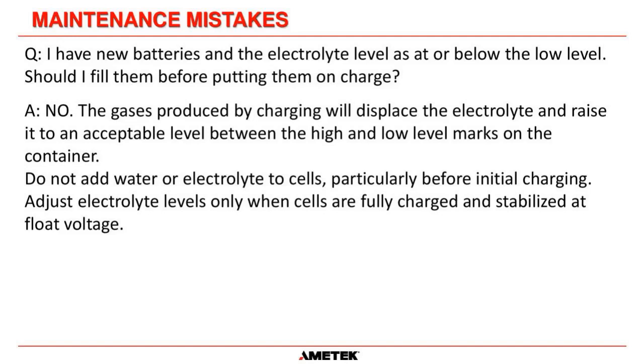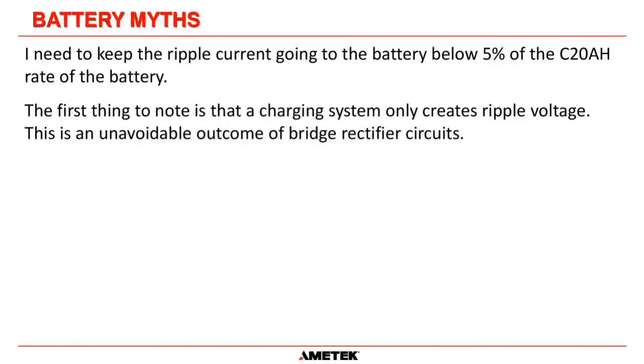So when you charge the plates, that sulfuric acid gets dispelled from the plate itself and increases the level of the electrolyte also. So do not add water or electrolyte to cells, particularly before your initial charge. Only adjust electrolyte levels when the cells are fully charged and stabilized at float voltage. Okay? So please bear that in mind.